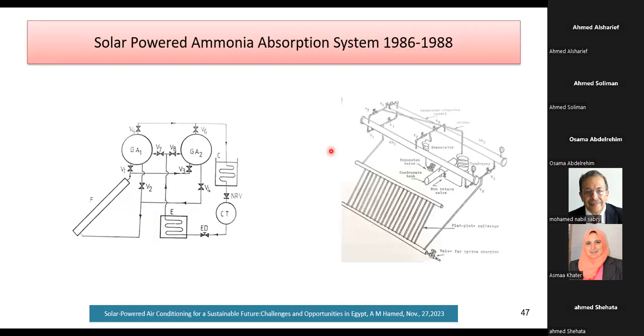And this was one of the oldest works we have carried out at Mansoura University. Really, it was my master's, from 1986 to 1988. This was an absorption cooling system powered by a flat plate collector, using ammonia-water, with ammonia as the refrigerant and water as the absorbent. And I remember that we reached in this system minus 6 degrees Celsius during the test of this system at that time.